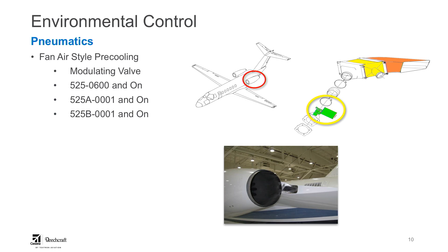Now you'll note on the CJ3s, on serials 327 and on, there is a dedicated exhaust vent for this pre-cooler. The other aircraft, earlier aircraft on 525 and 525A, as well as the earlier serial numbers on the 525B, may not have this. They do not have this on these models. And the reason is that air is vented into the pylon itself. But we learned through experience that on the CJ3, that air was just a little bit too warm and it was starting to discolor some of the paint.